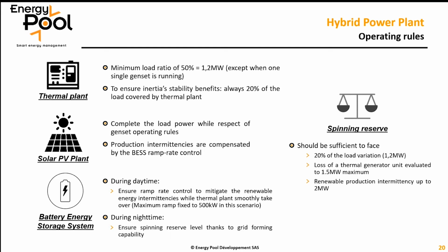For the solar PV plant, it will complete the load while respecting the genset operating rules. It means that the solar PV plant cannot cover more than 80% of the load for our case. And the power intermittencies will be compensated by the battery energy storage system's ramp rate control, also called the PV smoothing mode of the inverter. So for the battery energy storage system, during the daytime, it will do what I just mentioned, the ramp rate control of the renewable. And during the nighttime, we will use the grid forming capability to ensure the spinning reserve level.